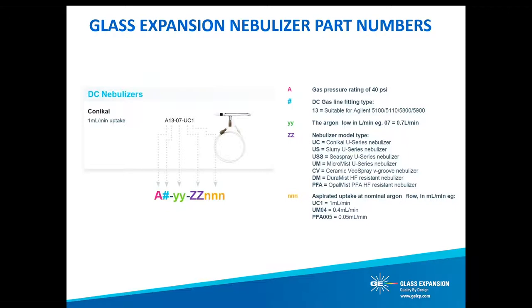Each of our nebulizer models is also designed for a specific liquid flow rate or range of liquid flow rates. You do not want to choose a low uptake nebulizer model if you're running your ICP at, say, 2 mils per minute, as it will degrade performance and lifetime. The liquid flow rate is indicated by the NNN in our part number nomenclature. It's also important to note that all of these uptake rates are the nominal self-aspiration rate. You can always starve a nebulizer with your peristaltic pump, but make sure you're selecting the nebulizer model for at least close to the highest uptake rate you'll be using in your ICP method.